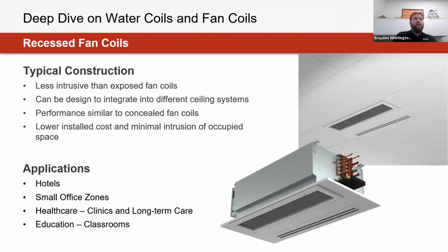Another version of what you might see here too is going to be recessed models. Essentially, you can visualize a lot of the times it might even be paired with even beam systems, but now you have a fan that's going to be drawing air through the coil itself, but installed in a 2x4 ceiling grid or 2x2 ceiling grid for essentially also allowing in these smaller spaces for having a lower installation cost, as you're not having to worry about any additional ductwork, and you have the existing grid system there too, but being an effective solution for adding some additional cooling or heating for these spaces and additional air changes there as well.